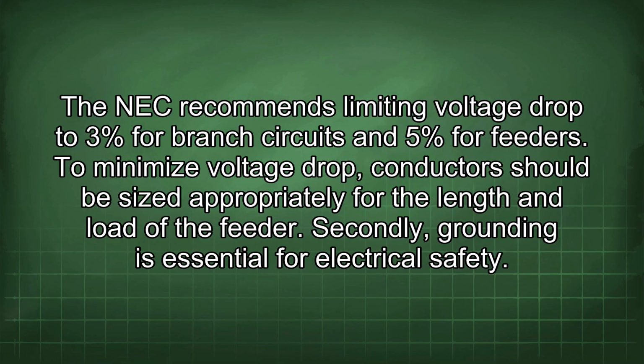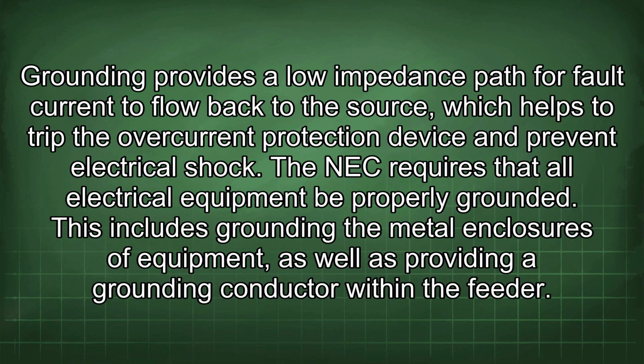Secondly, grounding is essential for electrical safety. Grounding provides a low impedance path for fault current to flow back to the source, which helps to trip the overcurrent protection device and prevent electrical shock. The NEC requires that all electrical equipment be properly grounded. This includes grounding the metal enclosures of equipment, as well as providing a grounding conductor within the feeder.